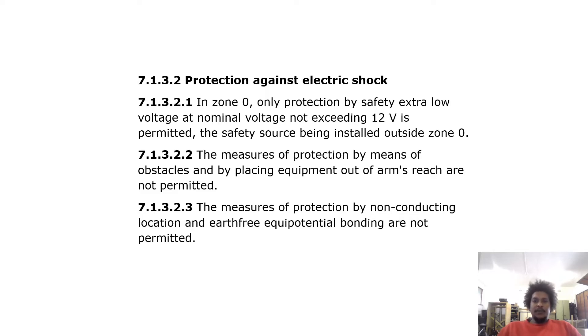Protection against electric shock in zone 0: only protection by SELV at a nominal voltage not exceeding 12 volts is permitted, with the safety source installed outside zone 0. The measures of protection by means of obstacles and by placing equipment out of arm's reach are not permitted. The measures of protection by non-conducting location and earth-free equipotential bonding are also not permitted.